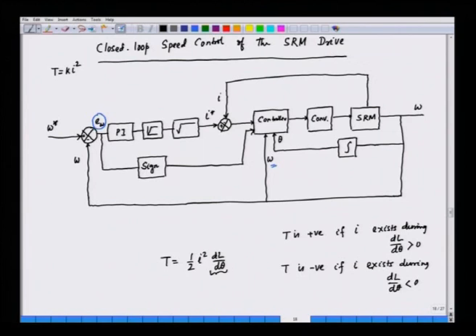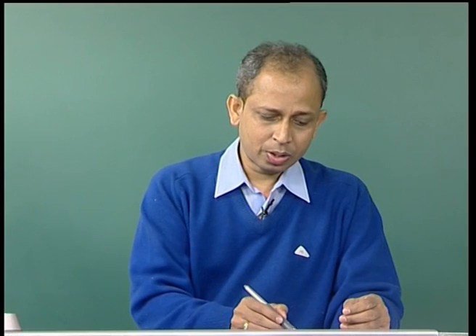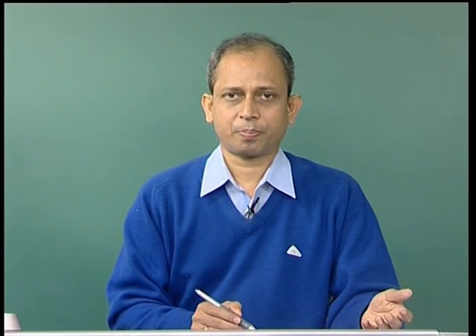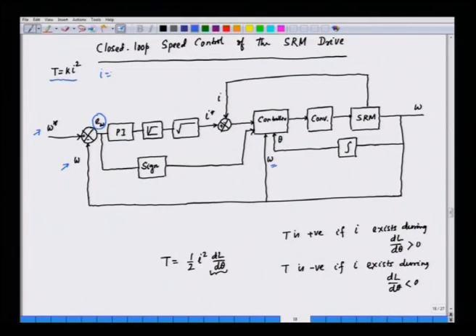This is the block diagram of the closed-loop speed control. We have the reference speed, and we compare this with the actual speed by having a speed feedback. Then we have the PI controller — the proportional integral controller — which gives something similar to the torque. We know the torque is given by K times I squared, so if you want to find out the current, current should be the square root of torque: I = sqrt(T/K). We have a square root block here, and this is the limiter that limits the maximum value of torque that can be produced.